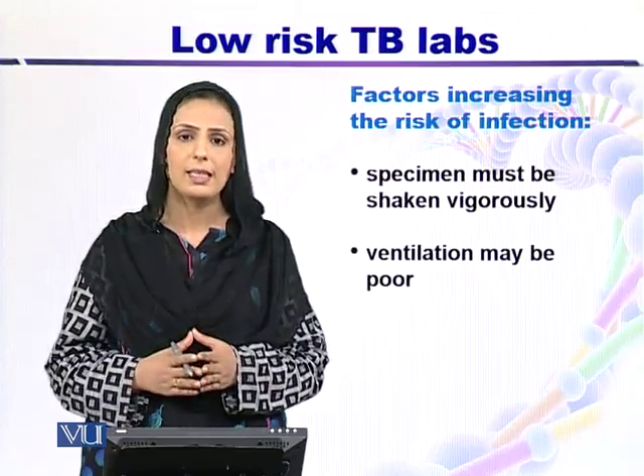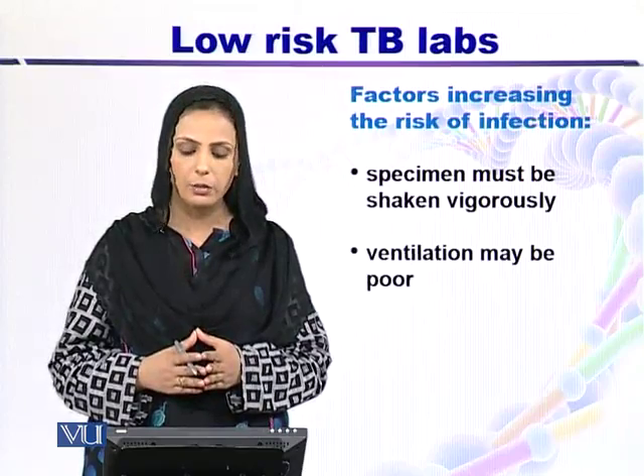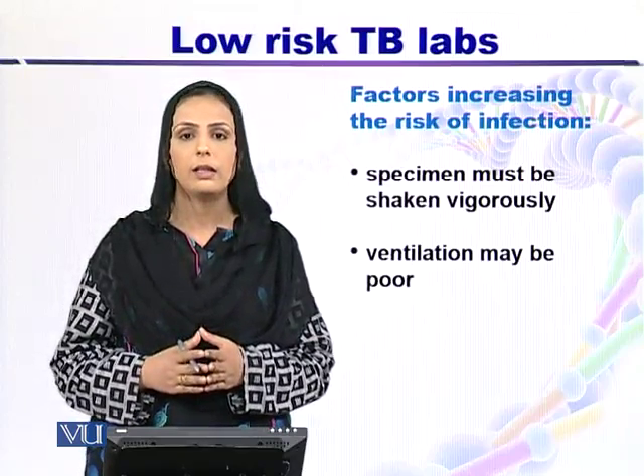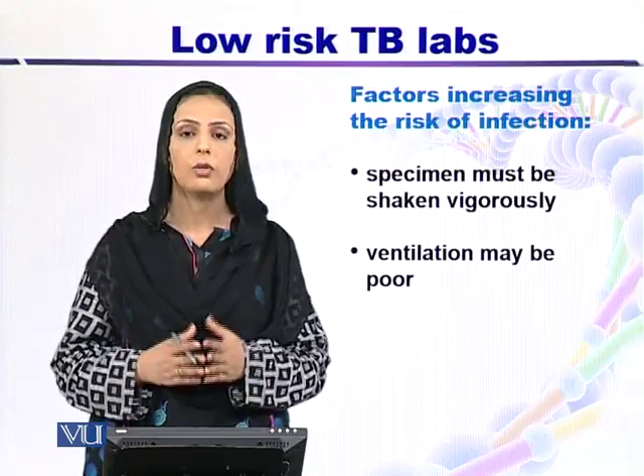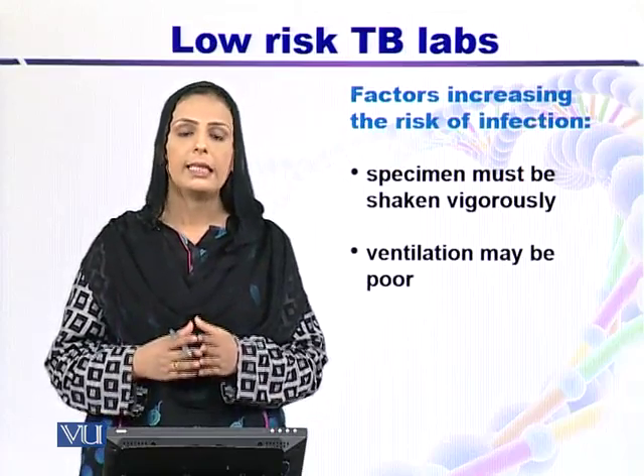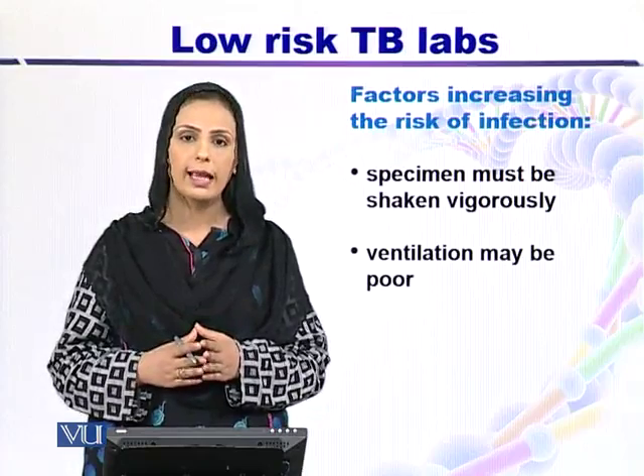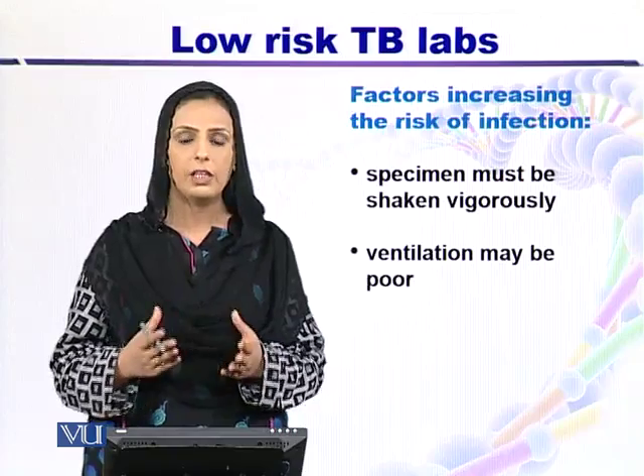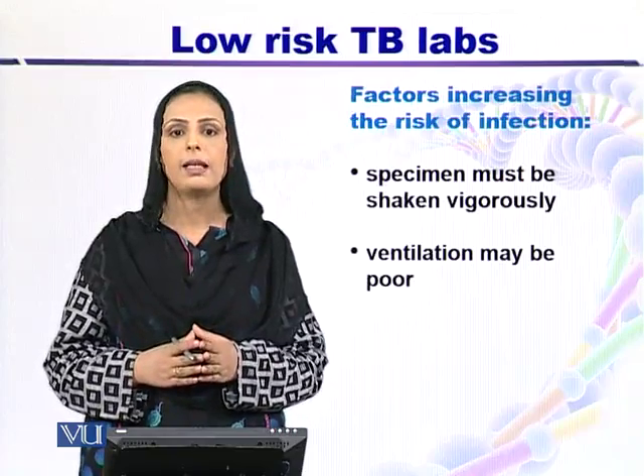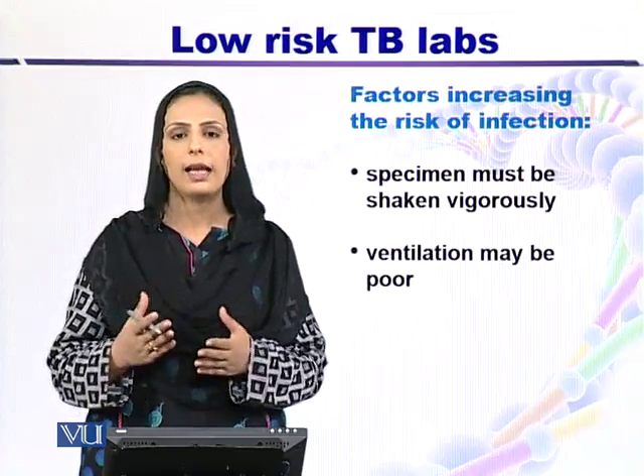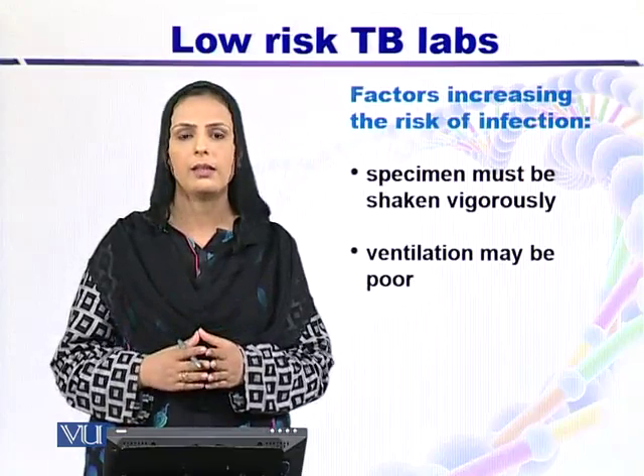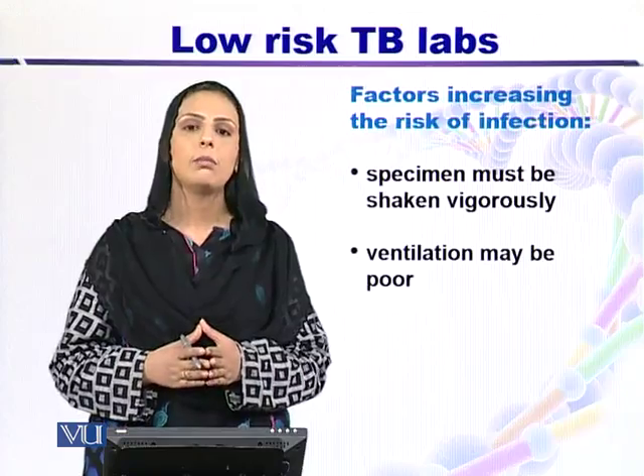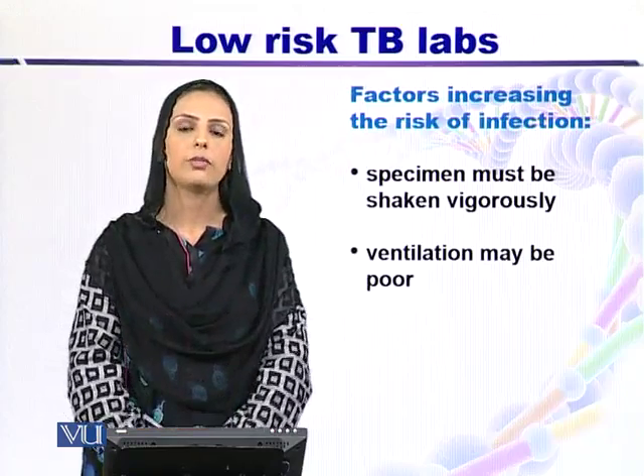Poor ventilation also increases infection risk. For low risk labs, directional airflow is required, provided by a mechanical ventilation system. However, if the local climate is appropriate, natural ventilation — simply by opening the windows of the lab — can be used as an alternative.